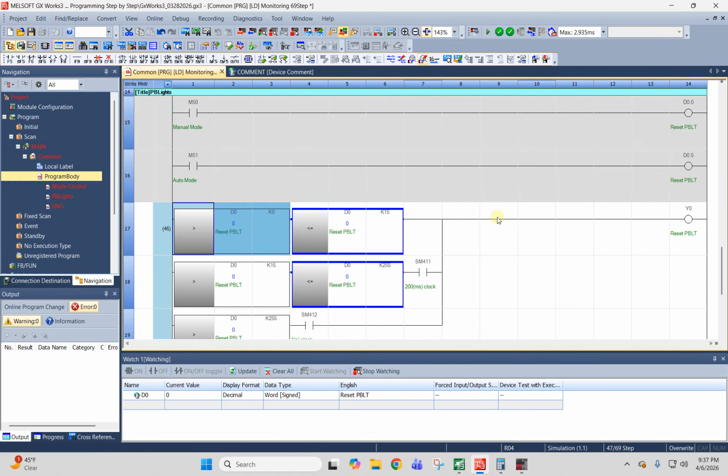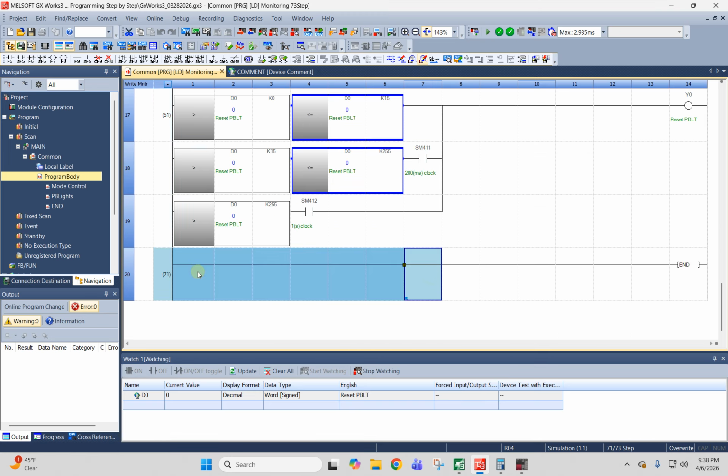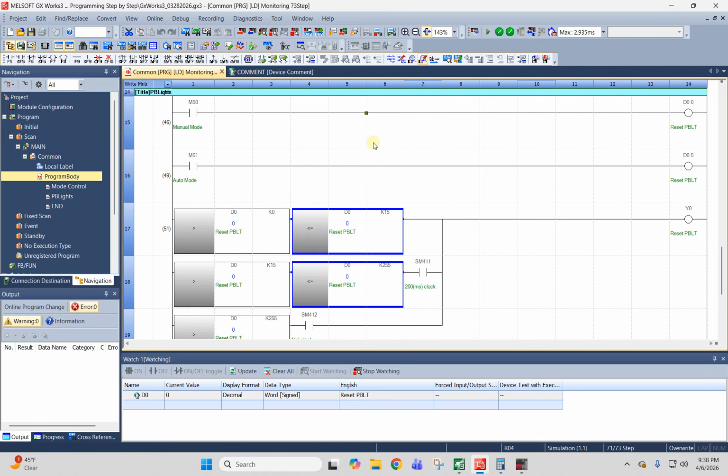So that's 2 separate modes, and you can fire separate bits to have different types of flashers on. If you want something to flash more, you put it into the higher bits. If you want it to not flash, you put it in the lower 4 bits. If you want to flash at a high speed, you put it to bit number 4, 5, 6, 7. Then you can add one more condition down here, and that way you have 4 separate ways of flashing indicators whenever you need. And you can reuse this logic.